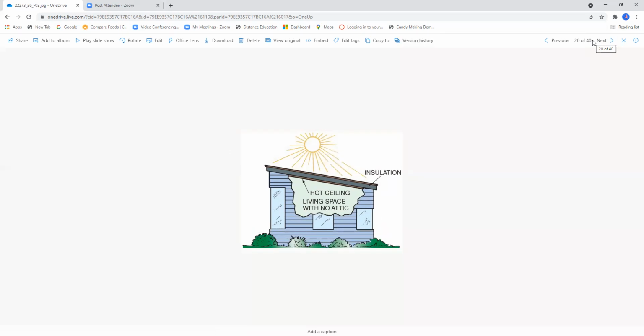Now, here's the problem. The ceiling stays hot all the time, the living space has no attic, and you've got to increase the cooling load based on this type of construction. If you are contemplating purchasing a house like this, I would highly advise you to think again. These types of roof construction, where you have an open beam concept with an insulation panel between the roof deck and the ceiling below, are going to be a problem as far as heating and cooling is concerned.